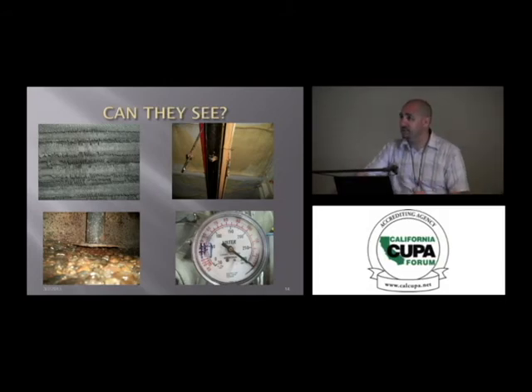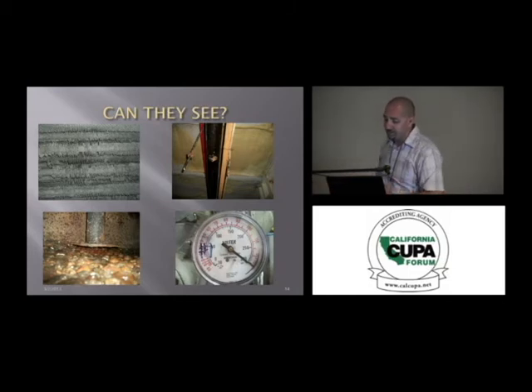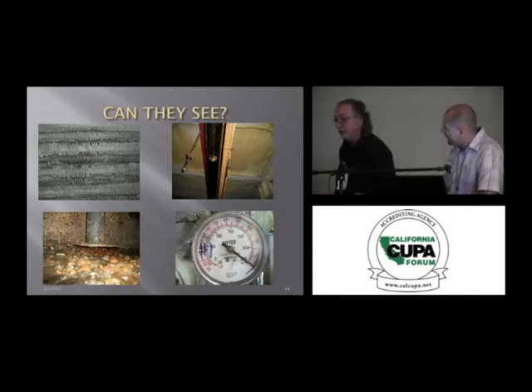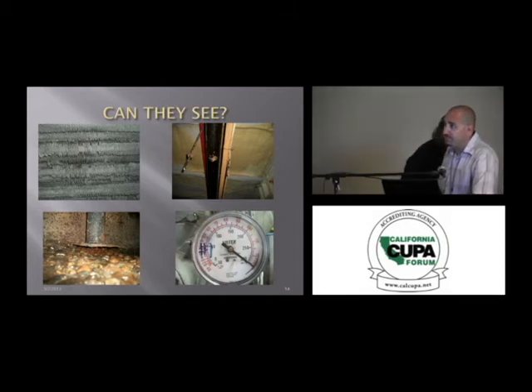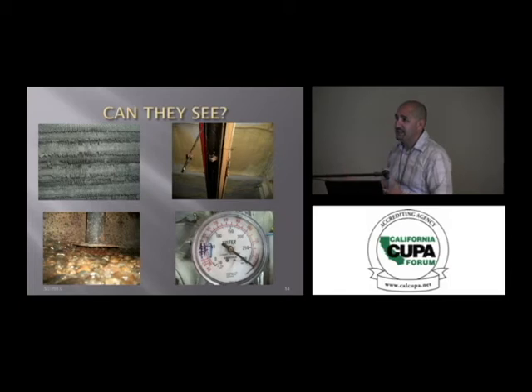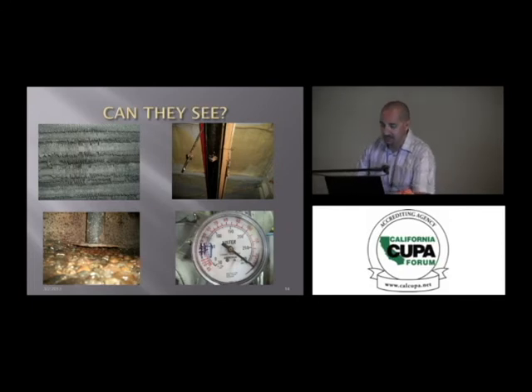And yeah, you see that bottom right-hand gauge. Can anybody tell me what's wrong with that gauge? Yeah, if you have a 300 psi relief valve, it's about to pop off. If it hasn't already. If you have a 250, it's popped off. Look at that pressure. That's right at around 300. Yeah, about 295. The reason it's like that is because they trapped liquid in that line, and they had hydrostatic expansion. There were 30-some gauges like this in that facility. And that's because the operator turned the wrong valve and didn't bleed off the liquid before they isolated that location. They trap it, and once the liquid is trapped, a little bit of heat is added. Again, it expands, and it's going to find its weakest point and make its way out and cause a stink about it.